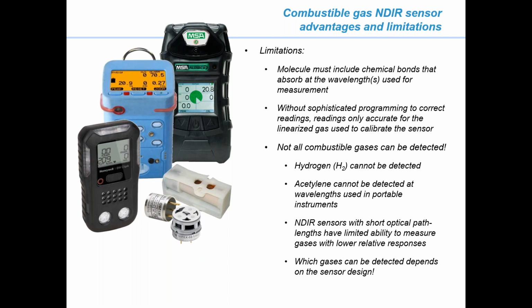And also, without sophisticated programming to correct, the readings are only accurate for the linearized gas curve used to calibrate the sensor. What that means more in just a moment. And of course, not all combustible gases can be detected. Hydrogen can never be detected by IR absorbance. It does not absorb IR. You need to use another sensor to detect hydrogen.